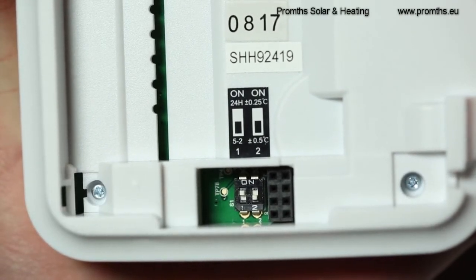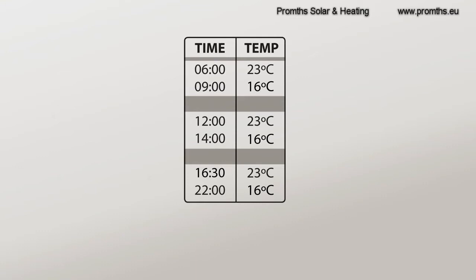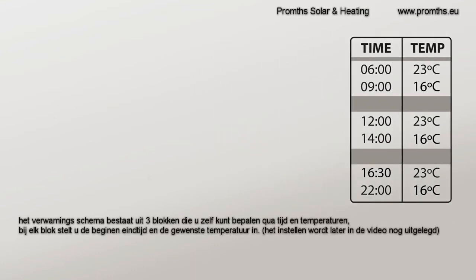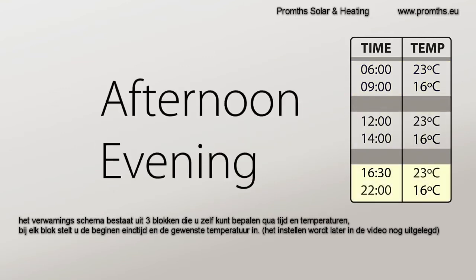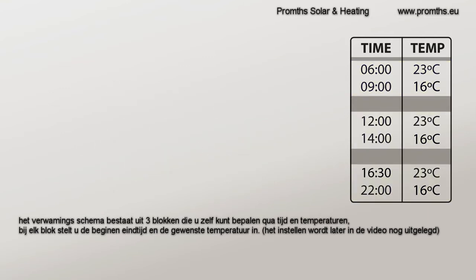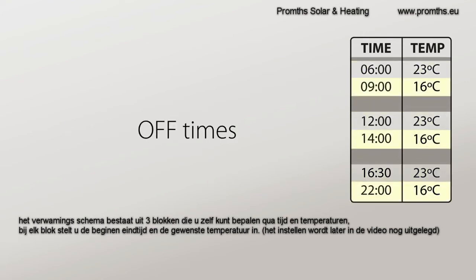The heating schedule is basically three events throughout the day. These are usually morning, lunchtime and afternoon or evening. Each event has two programs. The first is the on time and temperature. The second is the off time and temperature. This is an example of a typical heating schedule.